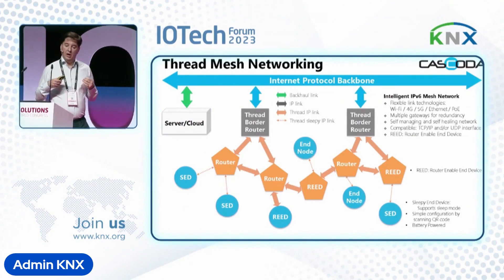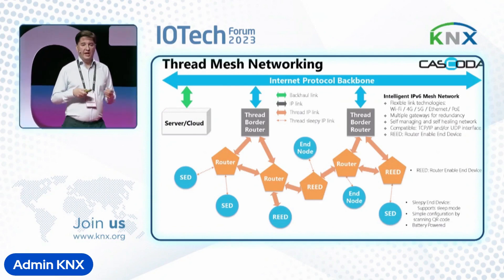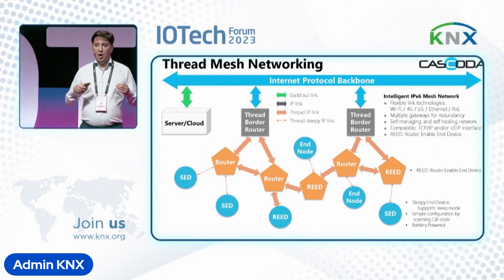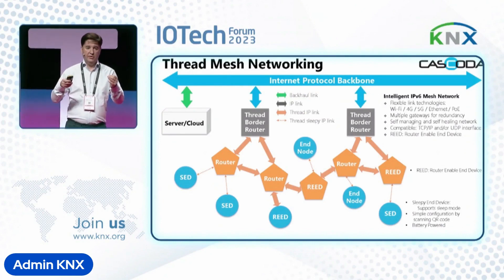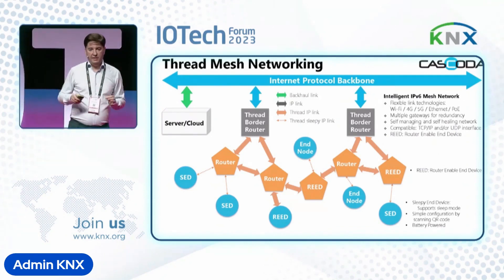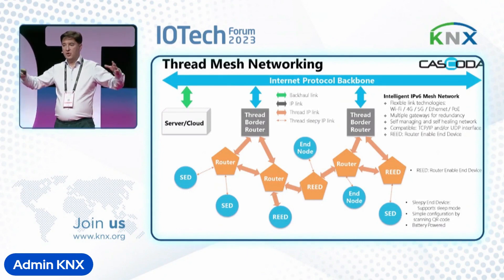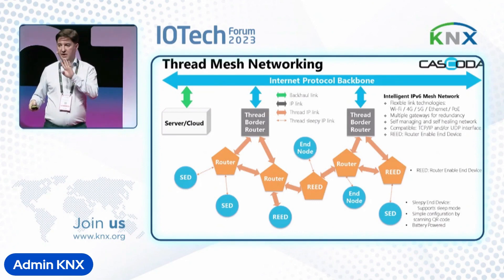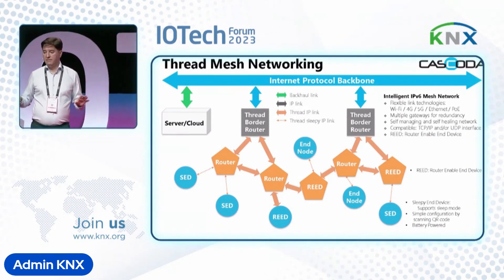Thread provides mesh networking capability — a seamless, self-managing mesh. This is very important for buildings because you don't need operators to get involved with the mesh. It will self-manage. Devices will upgrade themselves to routers dynamically if another device gets added to the network. As we build out infrastructure within buildings, it will seamlessly scale to massive IoT. Each radio frequency can support hundreds of devices, and we have 16 radio channels to choose from. That's why this is incredibly powerful for building automation.